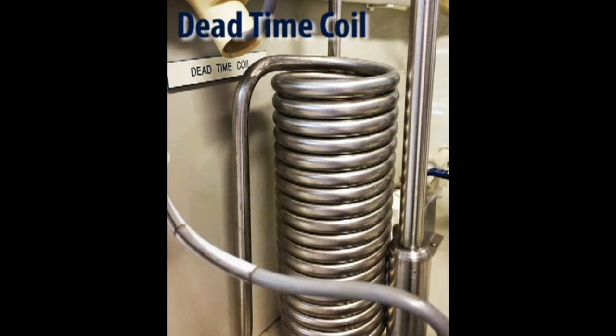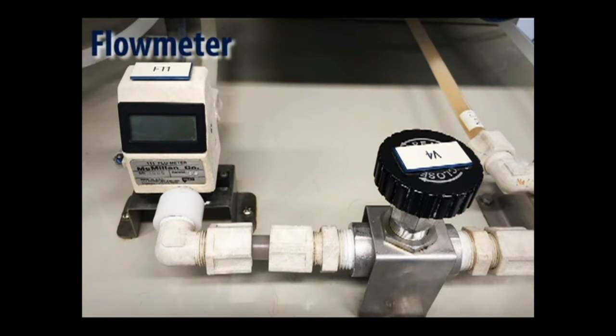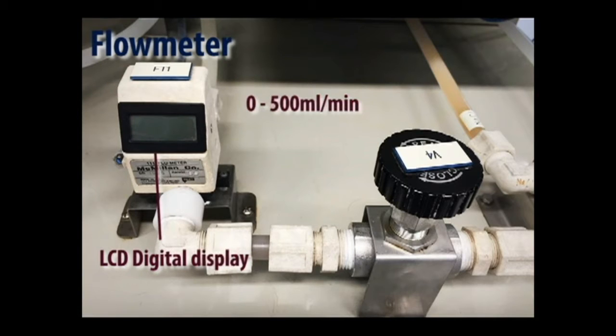The dead time coil is made up of stainless steel tubing. It can hold up to approximately 200 ml of the solution. The flow meter has an LCD display. It is ranged from 0 to 500 ml per minute and the output is ranged from 0 to 5 VDC.